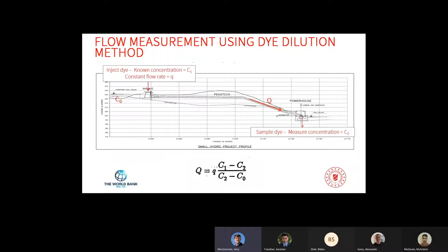That dye passes through the power tunnel and the penstock, and it must completely mix with the water in the penstock before it is sampled from one of the same taps that we measure pressure with. We will sample the dye that is coming out of the turbine, and effectively we can calculate the flow using this formula down here. C0, by the way, is the background concentration of dye in the water. It's typically very low, but you still need to account for that.